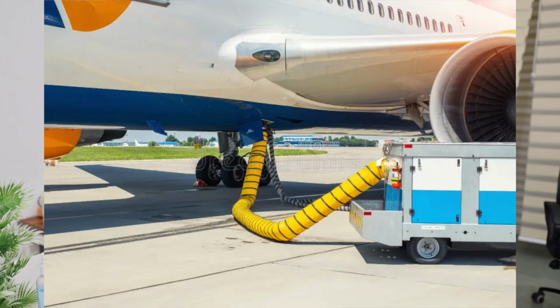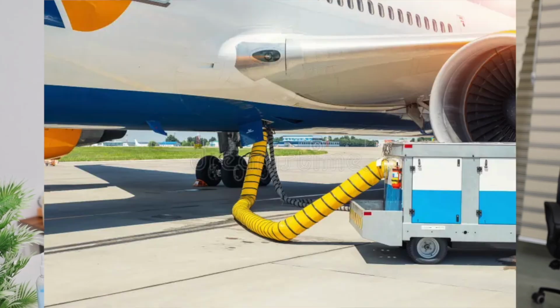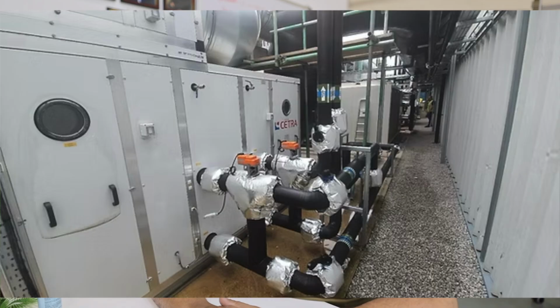When the aircraft are standing at the rotundas or the bridge, there is a yellow color hose connecting to the bottom of the aircraft. This is the Glycol connection, because that air conditioning system is separate, the Glycol air handling unit is there. In that air handling unit, there are 2-3 coils. The first coil, there is one AHU, the fresh air AHU. From the fresh air AHU, 20-22 degrees Celsius temperature. If, for example, your outdoor temperature is like 40, 48 or 50, whatever it is, the fresh air handling unit will decrease the temperature to 20 or 25.